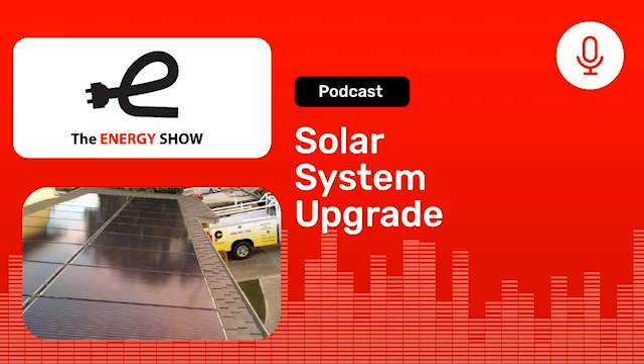If your system isn't SolarEdge, it's still okay because you can install optimizers. You add optimizers on all the panels. So you have 20 panels, you add 20 optimizers, and that's just some work that has to be done on the roof. You don't have to do any rewiring down below. It's just work that's done behind each panel. And if it's really old panels, let's say you have 40 really old 150 watt panels, we would put one optimizer on every other panel. And so we would use 20 optimizers. So that works out really, really well.